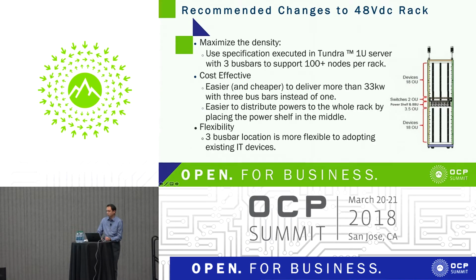The third reason is the flexibility. By using the 3 bus bars, it is actually also easier to convert the existing IT devices. For example, if you have an AC power 19-inch networking server, usually the AC power supply is on either side, maybe on the left or right or both.